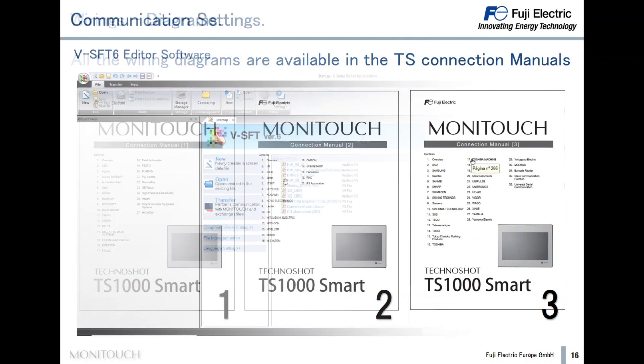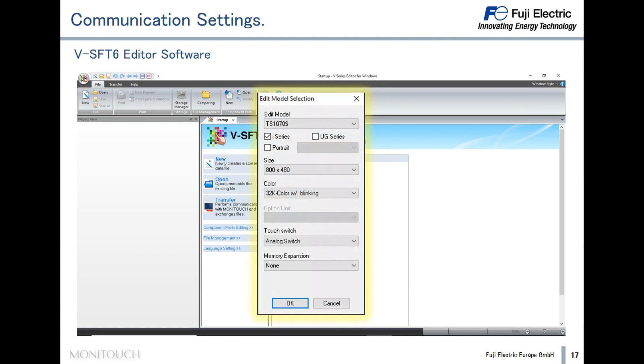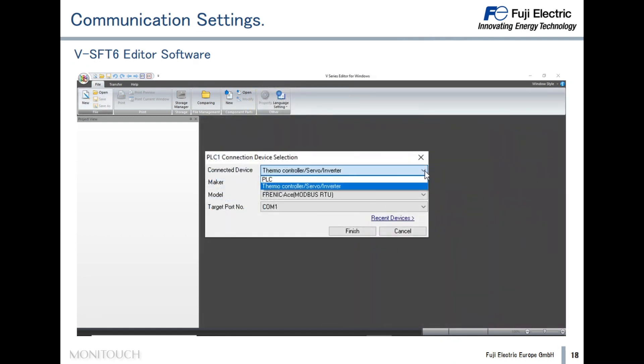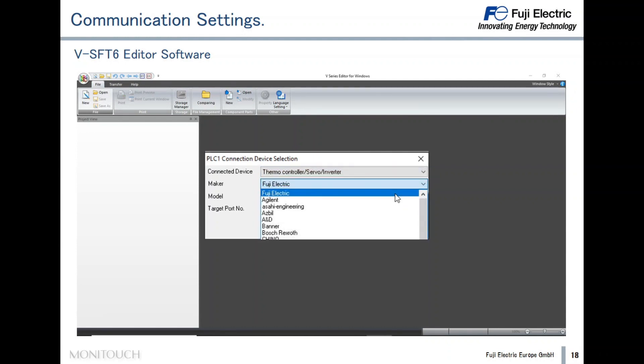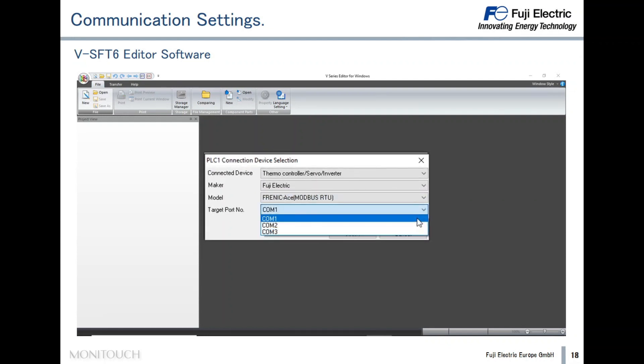Let's go into the communication settings in detail. To set up communication, the first step is to create a new project in V-SFT6, then select the Technoshot Smart as the HMI model, select Inverter as the connected device, select Fuji Electric as the maker, select the Frenic Ace Modbus RTU driver as the model, and finally select COM1 as the communication port, for example.